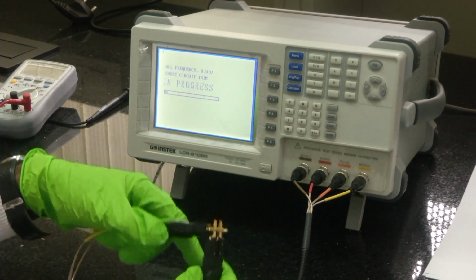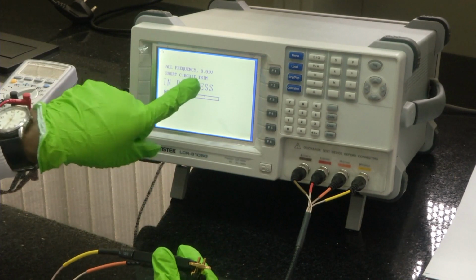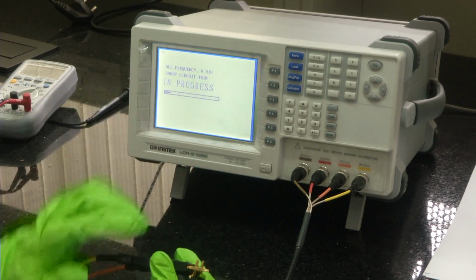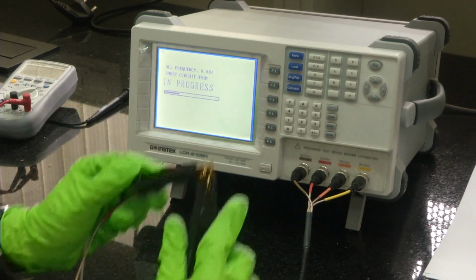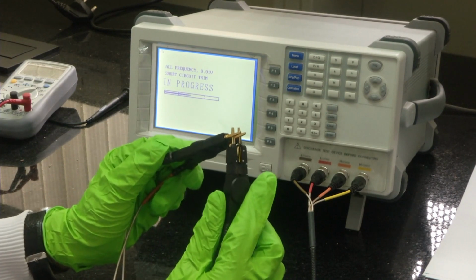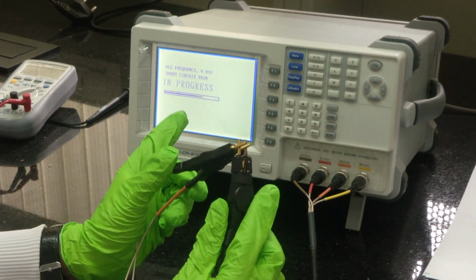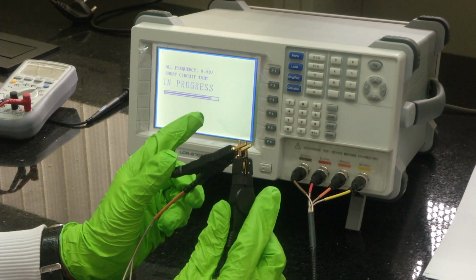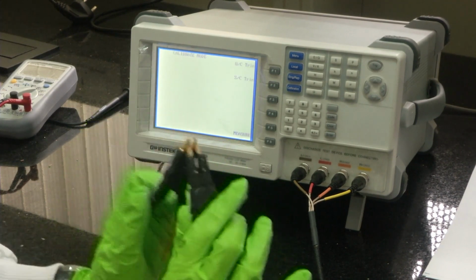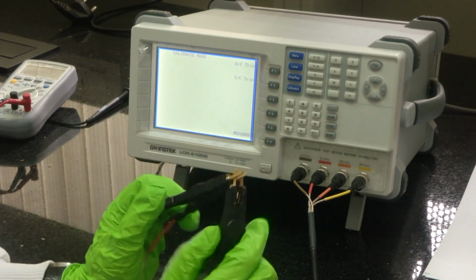Again the same thing will happen. So, all frequency short circuit trim it is doing and it is pushing 0.01 volt or 10 millivolt. I have kept it shorted and you can see the progress. Once that progress bar is complete, that means that the calibration is successful. Now, we are good to go ahead with measurement.